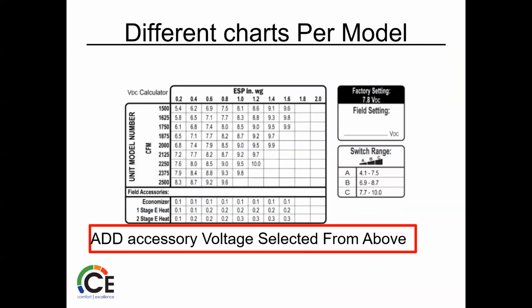You'll have to have a manometer again, as I said earlier. Make sure you guys have a manometer in their bag. It's a huge thing when we come to commercial. So we're going to have to do a basic ESP. Now, if you had a really good engineer, maybe he already told you what the design was on the building. If you're doing a replacement unit, you're going to have to do an ESP check. So you have to know that.